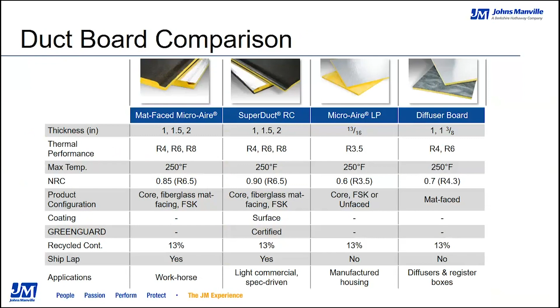One thing I want to address on duct board: all Johns Manville duct board products with a shiplap have a factory molded shiplap, meaning what you're seeing in the picture is a closure system for the longitudinal joint of that duct board system. As it's fabricated, the female shiplap and male shiplap come together and form a nice closure system that allows you to take that duct, staple it with outward clenching staples, and run UL 181 tape down to close it out. So we have a factory applied molded shiplap, a really nice feature on all our duct board products.